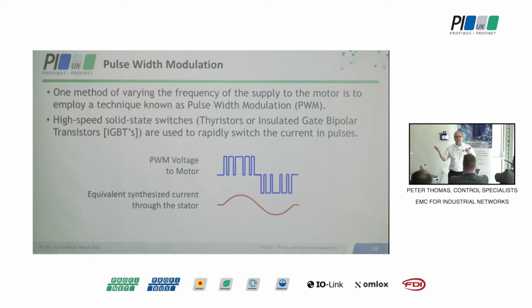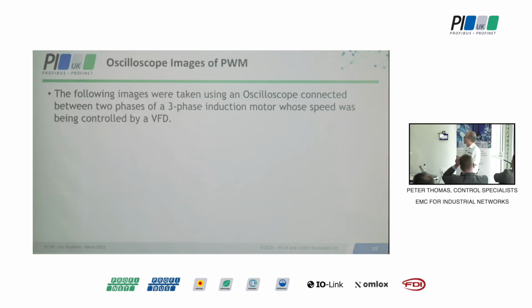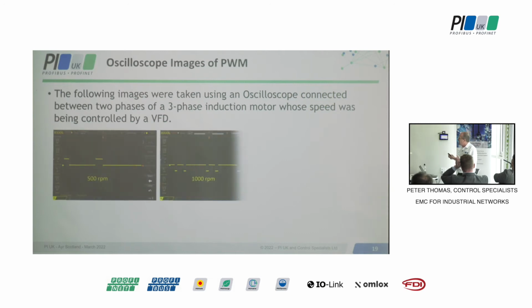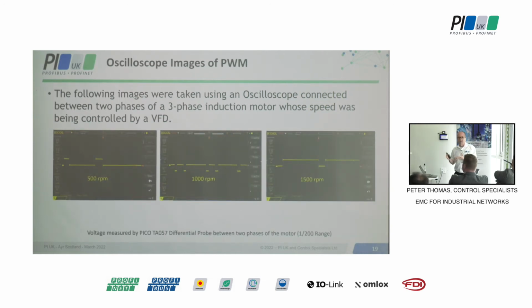It varies between 4 and about 16 kilohertz. So 16 kilohertz, imagine switching an electrical contactor on and off at 600 volts 16,000 times a second. Despite the fact that it might fall to bits after a very small time, you are instantly thinking of noise. It must be a noisy device, and by definition it is. But it gets even worse than that. So VFDs by nature are noisy devices.